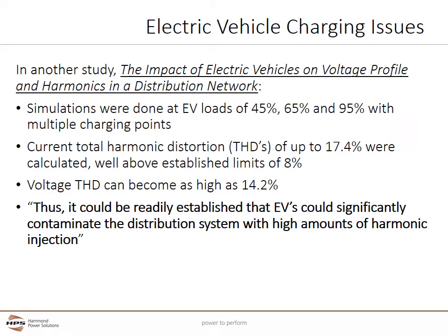In another study, The Impact of Electric Vehicles on Voltage Profile and Harmonics in a Distribution Network, simulations were done at electric vehicle loads of 45%, 65%, and 95% with multiple charging points. Current total harmonic distortion of up to 17.4% was calculated. 17.4% is well above the established limit of 8% total harmonic distortion current, established by the IEEE 519-2014 standard. Voltage total harmonic distortion was also calculated as high as 14.2%, which was also well above IEEE 519 levels. It was the finding of the study that it could be readily established that EVs could significantly contaminate the distribution system with high amounts of harmonic injection.